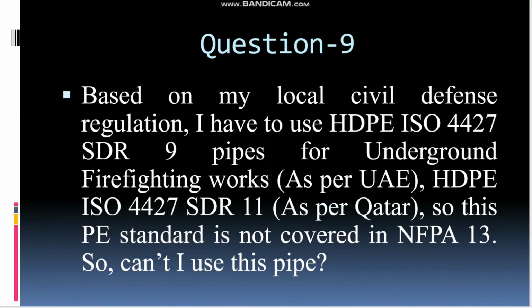So here the question is, based on my local civil defense regulation, I have to use HDPE polyethylene pipes, ISO 4427 SDR 9. SDR 9 is for the thickness. So for pipes for underground firefighting works, as per Qatar Civil Defense, HDPE ISO 4427 SDR 11 minimum pressure rating should be there. So this PE standard is not covered in NFPA 13.